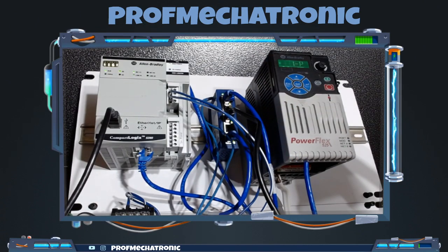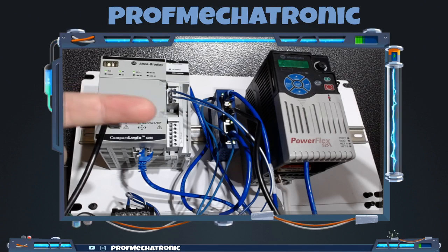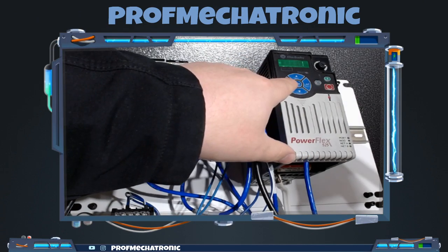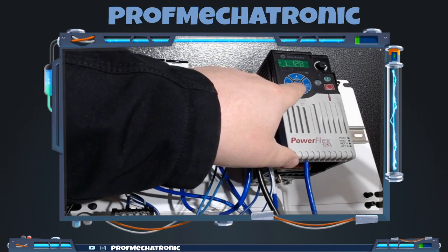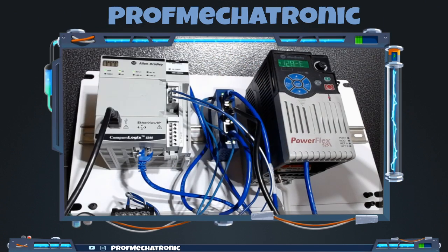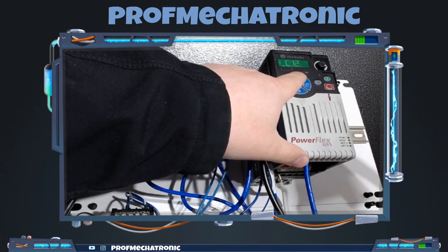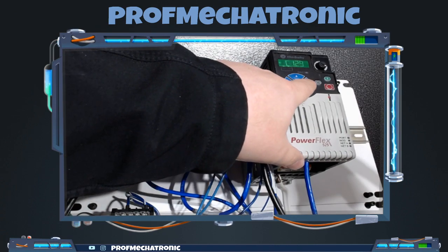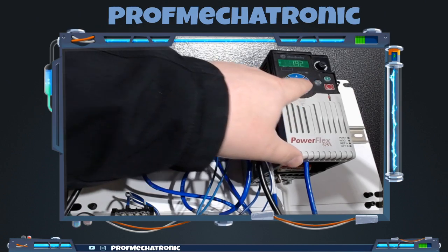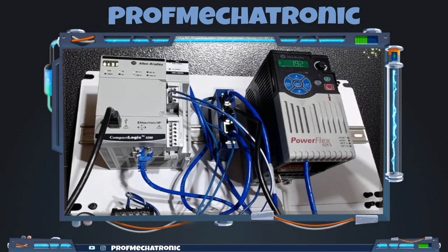We actually want to set this to parameter C128. Parameter C128 is for parameters. This allows us to hard code the IP address for this device inside of the actual parameter setup. And conveniently, right after setting C128, we can go into C129 and hit enter. C129 gives us our first octet of our IP address.